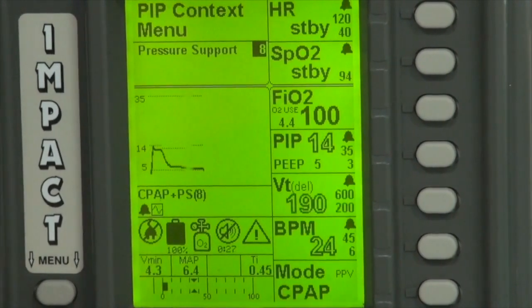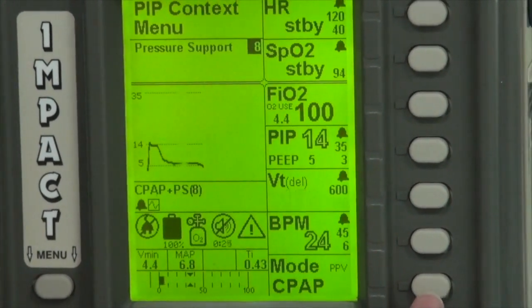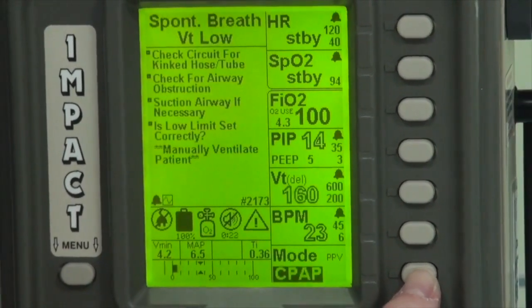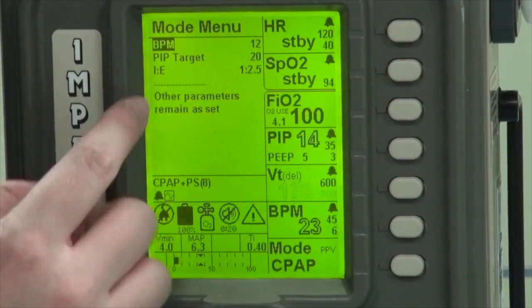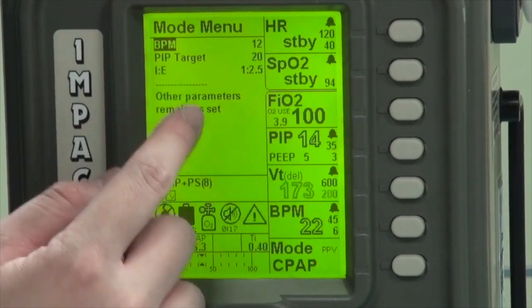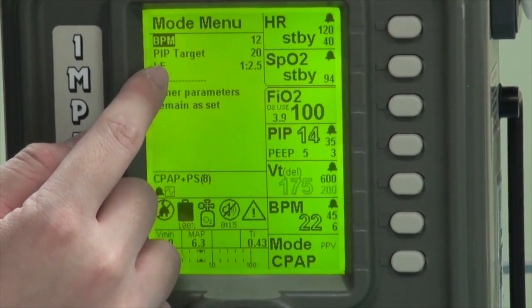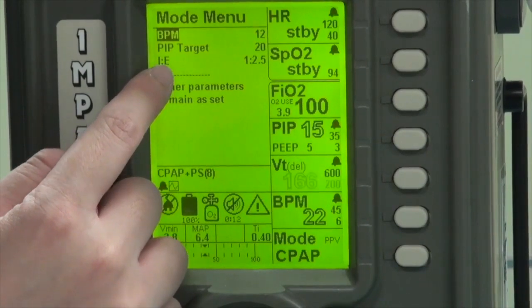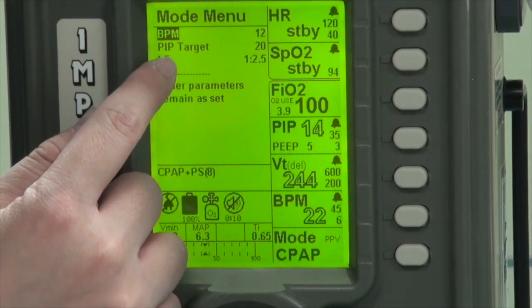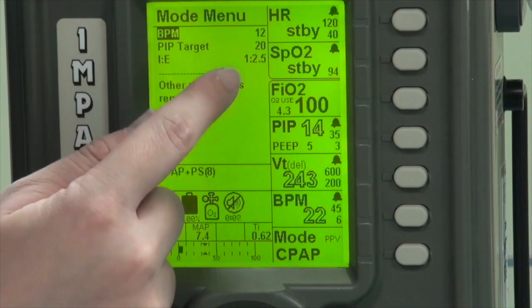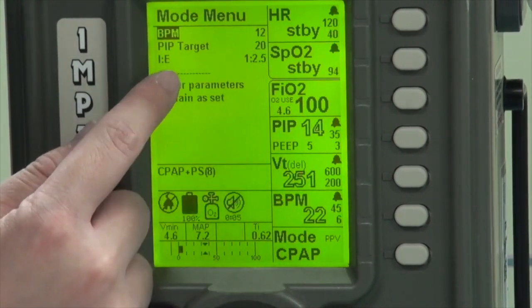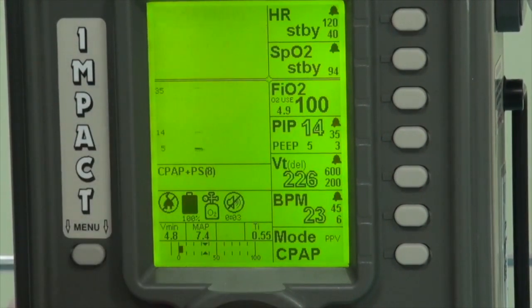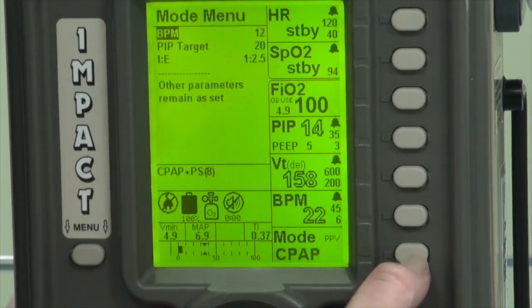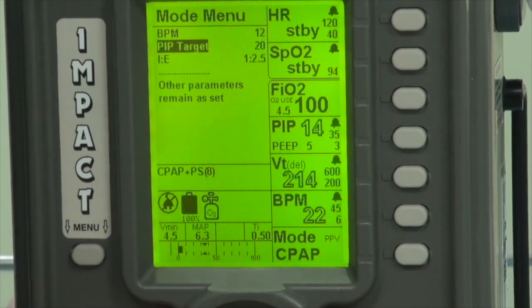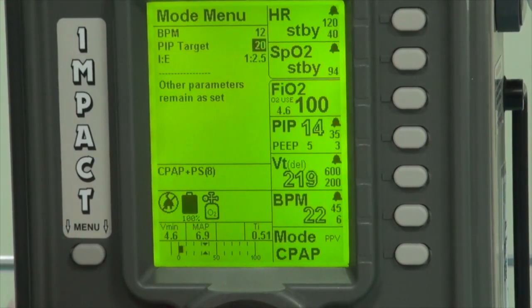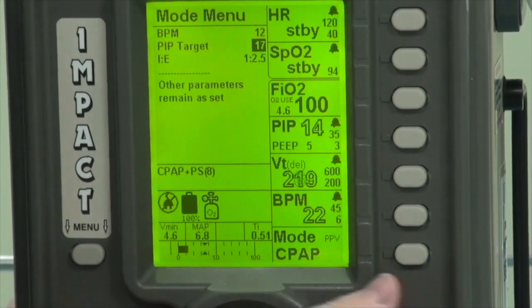In order to set the apneic settings, press and hold the mode button. We can see mode menu, breaths per minute, peak inspiratory pressure target, and I to E ratio. Take note that the peak inspiratory pressure target will include our PEEP, meaning our driving pressure will be 20 minus 5, or 15. If we want to decrease it, we can go to PIP target, confirm that you want to make this change, adjust accordingly, and confirm.